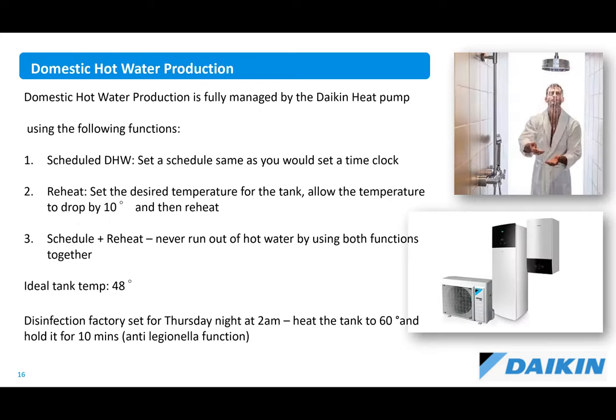restrictions around it. Domestic hot water production is fully managed by the heat pump schedule. So it will allow you to set your schedule for, you know, morning and evening, or you can use a reheat function. This allows the tank to drop by 10 degrees and then reheat to the set temperature of the tank. You can use both functions together so you never run out of hot water. The ideal tank temperature for efficiency is 48 degrees, and there is a disinfection function that's factory set for once a week. It'll heat the tank up to 60 degrees and hold it there for 10 minutes.